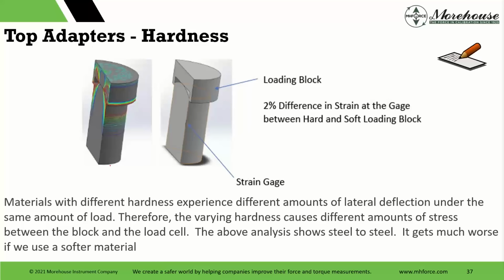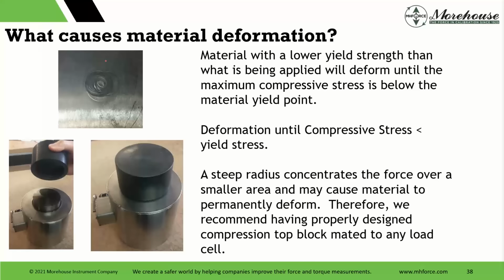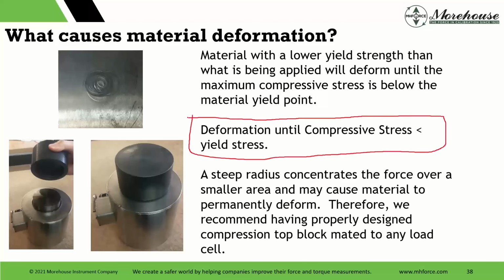So what happens here? Top adapters of material with different hardness experience different amounts of lateral deflection under the same amount of load. Therefore, the varying hardness causes different amounts of stress between the block and the load cell. And above, we're showing steel to steel. It gets much worse if we use softer material. What happens as far as safety is that material with a lower yield strength than what is being applied will deform until the maximum compressive stress is below the material yield point. So right here, deformation until compressive stress is less than yield strength. And then all of a sudden we start to mark things. And when we start to mark things, we create unflat, unlevel potential loading surfaces. And if we continue to mark this, and we have loading surfaces that are not flat, then we go back.